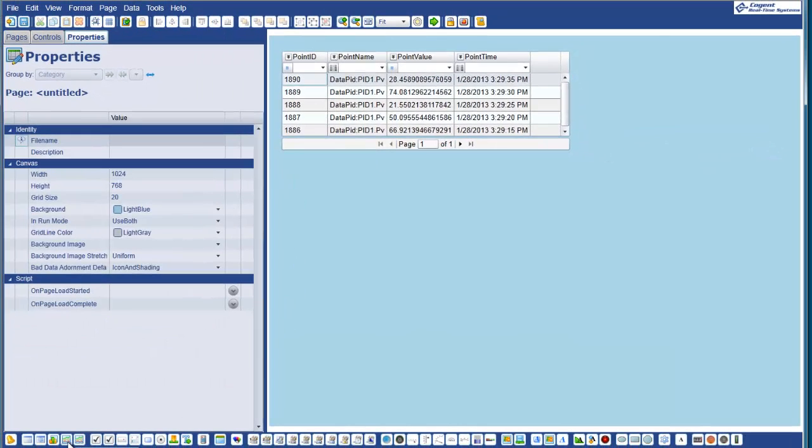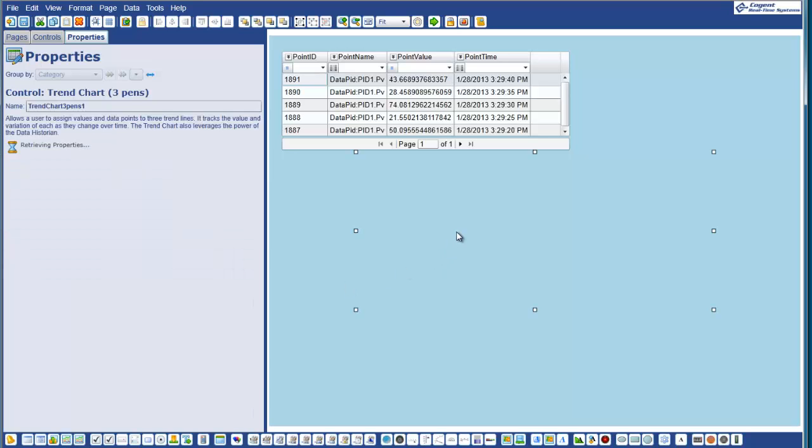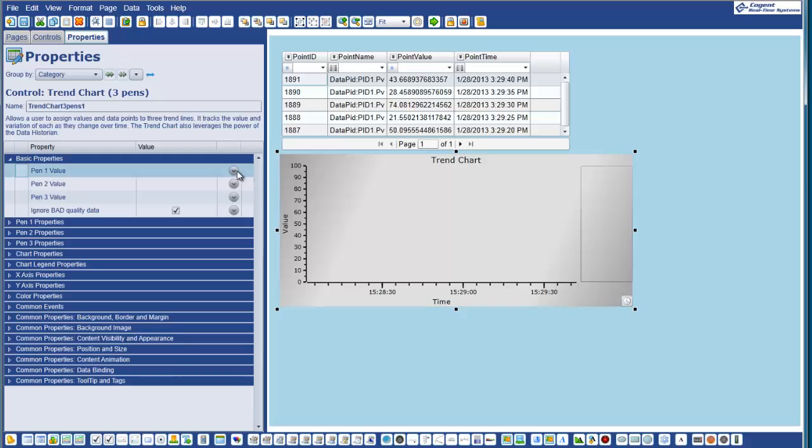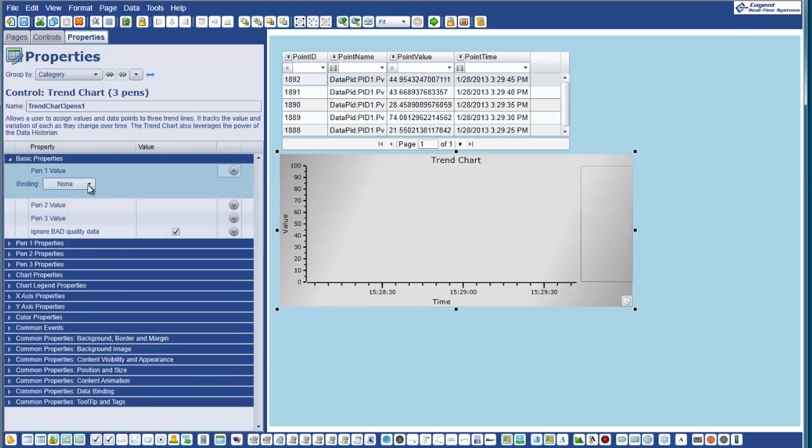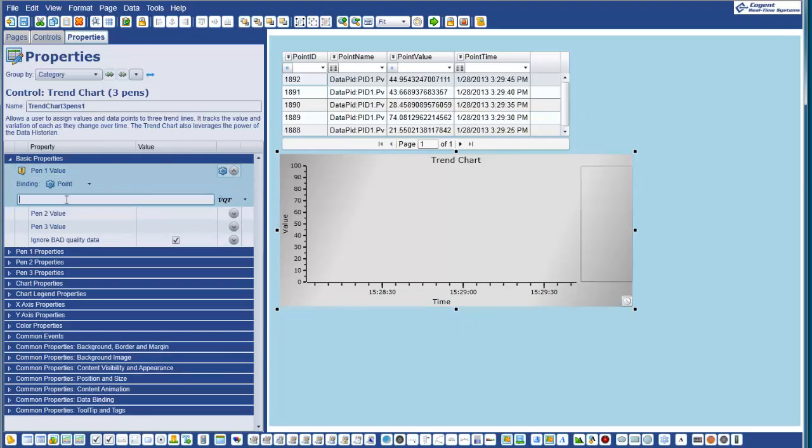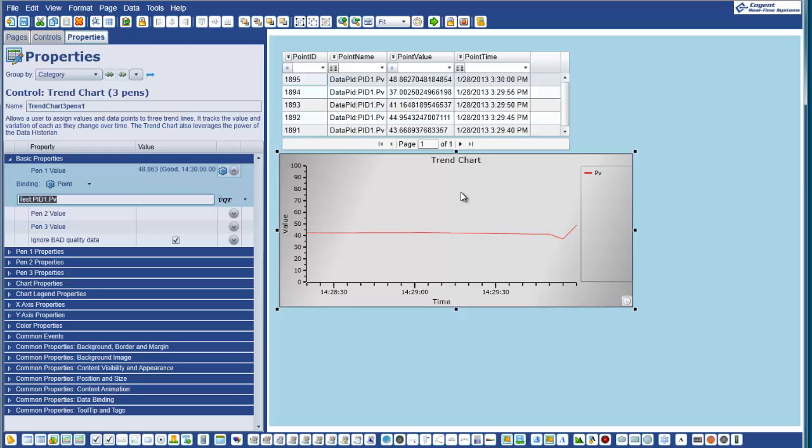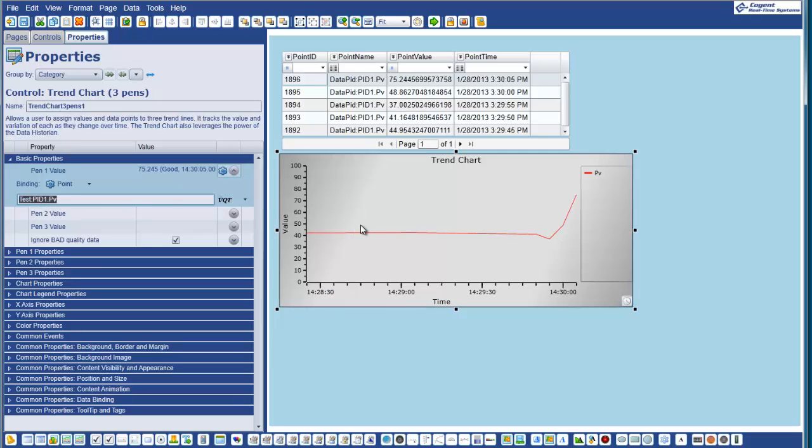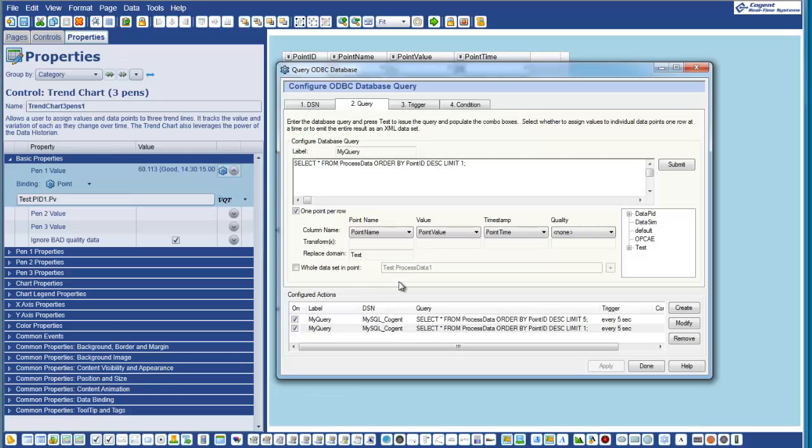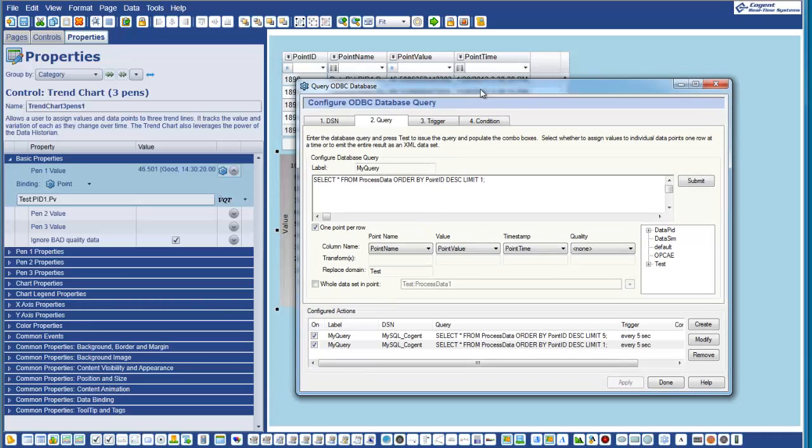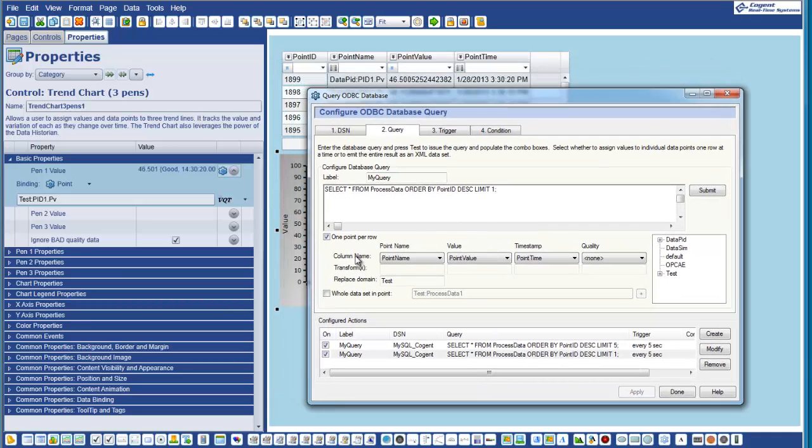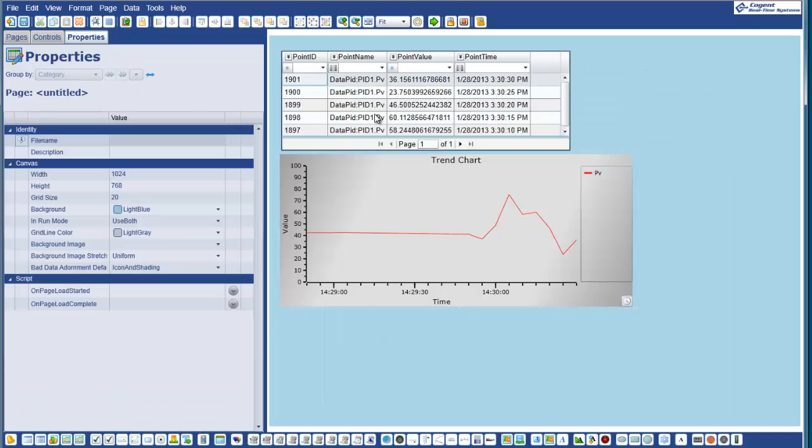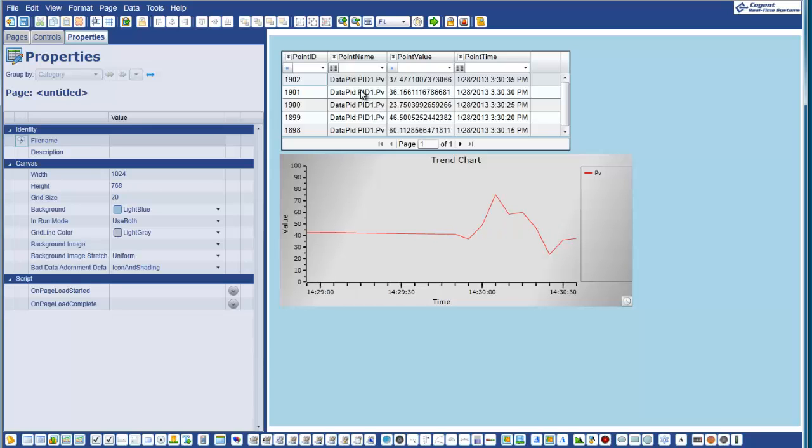But this single point value we can now use, if we go back to WebView, I can now put a trend chart on the page. And I can bind PEN1 to a data point. Let's say in my test domain I want to pick the PID1PV value. And then every five seconds as that query executes and we get a new value stored in the data hub for test.pid1.pv, our trend chart will pick up the data change and we'll plot that. So you see what we've done is we've configured two actions within the data hub, both reading from the same database. One of them is creating a single point with a value that's changing that we're mapping to a trend. The other one's creating a data set that we're displaying within the new filtered point table within WebView.